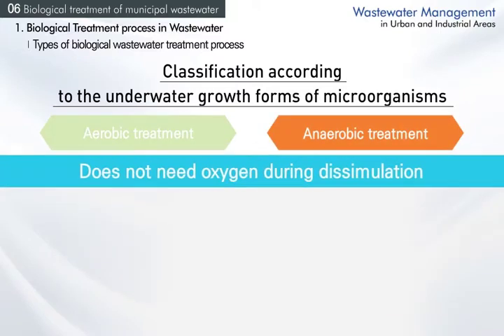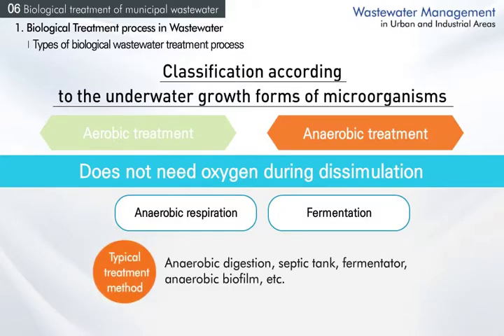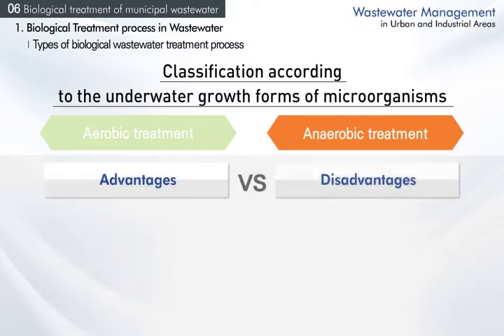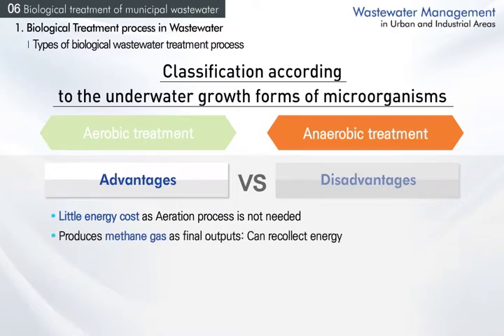Anaerobic treatment does not need oxygen for microorganisms to dissimulate and can be divided into anaerobic respiration and fermentation. Common treatment methods are anaerobic digestion, septic tank, fermentator, and anaerobic biofilm. Since anaerobic treatment does not need aeration for oxygen supply, its energy cost is cheaper than aerobic treatment, methane gas is produced as a final output enabling energy recollection, and it produces little wasted sludge.